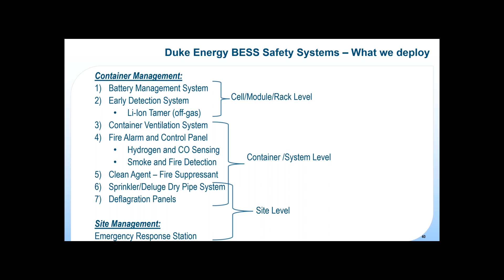Last but not least, we don't want any personnel to enter a site without Duke Energy's approval. So we have an emergency response station placed at the front of the site to keep our first responders safe, giving them fire safety information, off-gas event information, control of the exhaust systems, and access to the deluge systems. That's standard on every site.